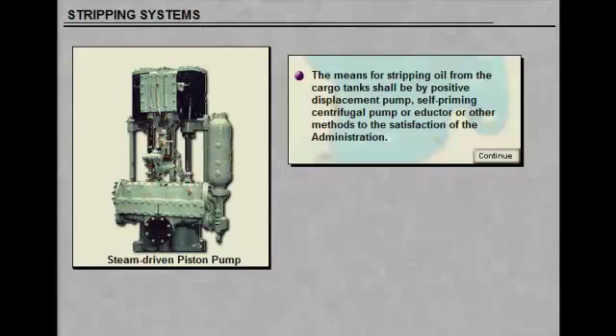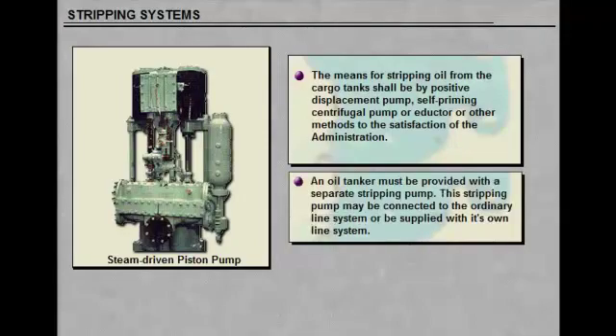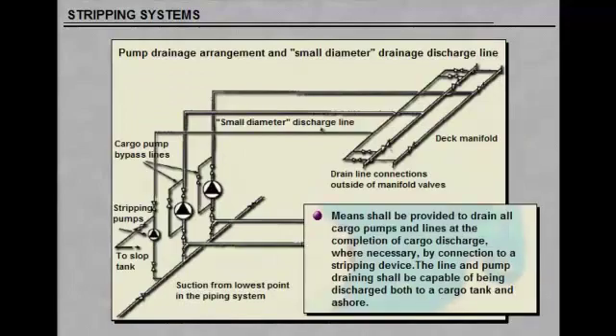Means shall be provided to drain all cargo pumps and lines at the completion of cargo discharge, where necessary, by connection to a stripping device. The line and pump draining shall be capable of being discharged both to a cargo tank and ashore. For discharge ashore, a special small diameter line shall be provided for that purpose and connected outboard of the ship's manifold valve.